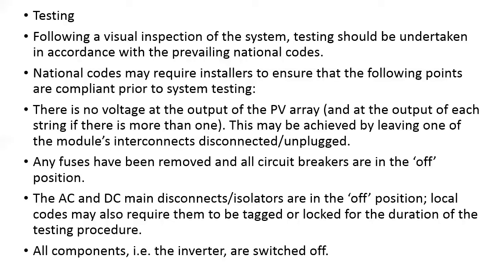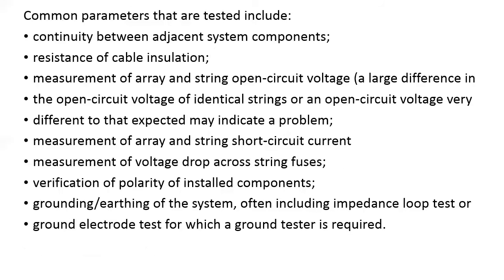Some of the common parameters that are tested include continuity between adjacent system components. We have to check the continuity between the adjacent system components. The next one is the resistance of the cable insulation. We know that the insulation resistance is one of the important things which we have to monitor.